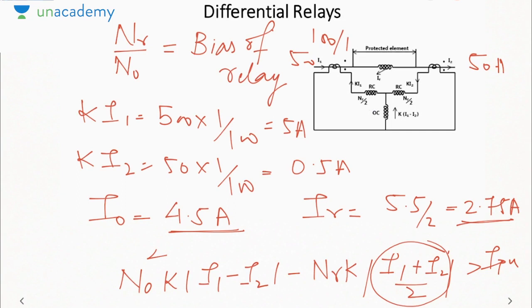Why is it called percentage? Because this factor of NR by N naught will be forming, which is called the bias or the percentage differential relay. So this way we have removed that problem of saturation or mismatching current transformer.